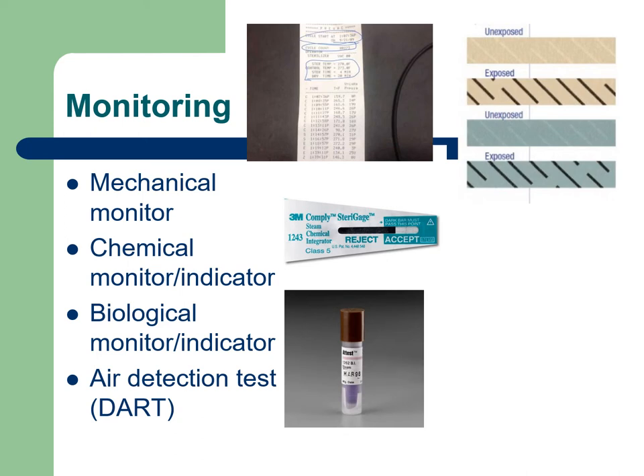Biological indicators. This little guy, remember, is loaded with a live spore. This one for steam sterilization is Geobacillus stearothermophilus. There is a different one for EO, but they work in the same way.